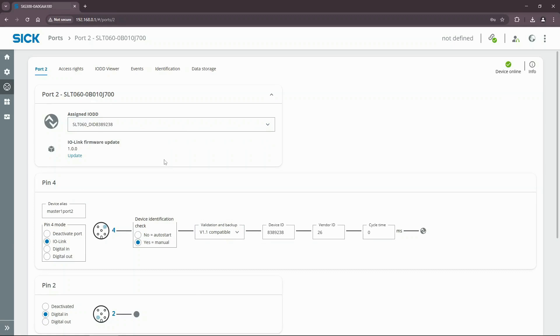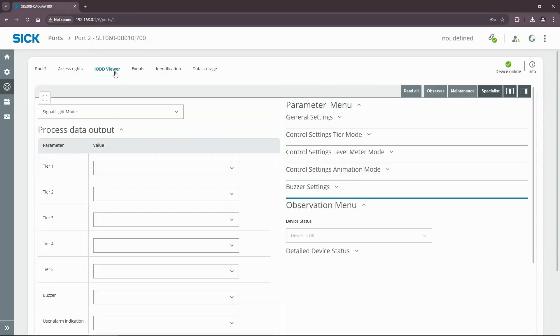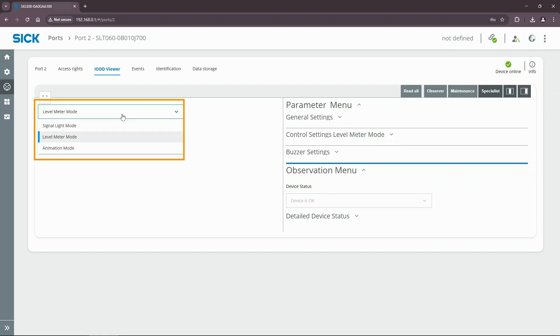After you finish configuring port 2 with the SLT060, open the IODD viewer tab and make sure that the level meter process data mode is selected. This mode enables the SLT to receive an integer value and indicate the corresponding level with LEDs.